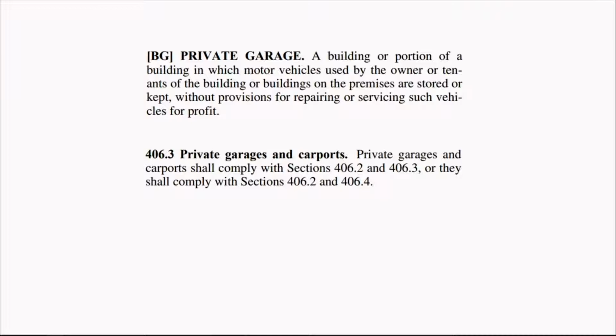First, we have the definition, what is a private garage? It's pretty clear that what we're proposing here is a private garage. 406.3 further defines the private garages and specifies that they shall comply with sections 406.2 and 406.3, or they shall comply with 406.2 and 406.4. 406.2 covers standards for all motor vehicle related occupancies. 406.3 is specific to private garages, and 406.4 specifies a slightly more restrictive set required for public parking garages, both open and enclosed.